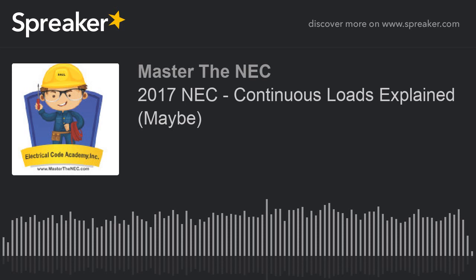Okay, so I've got 5 current carrying conductors. So when I've got 5 current carrying conductors, the first thing I need to do is remember I've got 90 degrees C insulation. Always remember that. I'm going to go over to Table 310.15(B)(3)(a), which is one page in front of 310.15(B)(16), and you'll notice that 4 to 6 conductors are treated as 80%. So we want to turn this into a decimal, so that is 0.80. Okay, so we write that down.